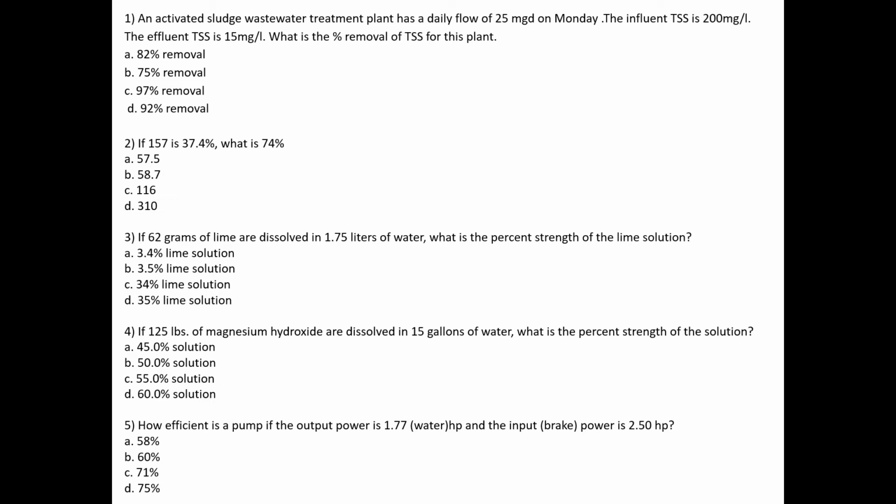friction loss in the pipe, restrictions in the pipe, flow meters in the pipe, bends in the pipe, all of that stuff, the lining of the pipe. If there's corrosion on the inside of a pipe, that's resistance against that water. That stuff makes a difference. In this particular problem, it says to meet the demands of the flow with the head requires 1.77 horsepower. That's the water horsepower. That's just the water going through the pipe.